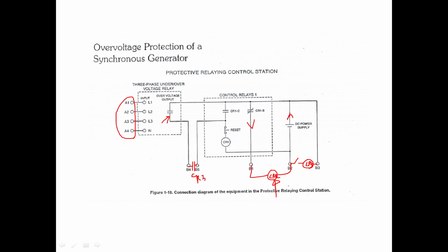Initially the current is flowing through CR2. When there is a fault, what will happen? This contact will close and there will be a red color light. The red light indicates that the relay has sensed the fault, but it will not take a control action. If you want it to take a control action, you have to manually close the CR3 contact. When this closes, the current can flow through this closed contact and through CR1, so the CR1 coil is energized.